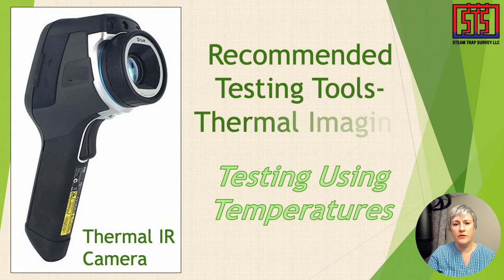Testing using temperatures. Measuring the trap's inlet steam temperature is the first step in the process of testing for steam trap failure. The temperature at the trap's inlet should be near its saturated steam temperature. In some cases, such as subcooled or superheated steam, the temperature will be lower or higher than its saturated steam temperature. Temperature can be extremely useful when trying to determine if a trap is blocked or its condensate capacity is insufficient. This is because condensate backs up and lowers the trap's temperature.